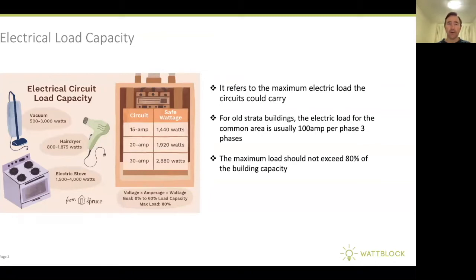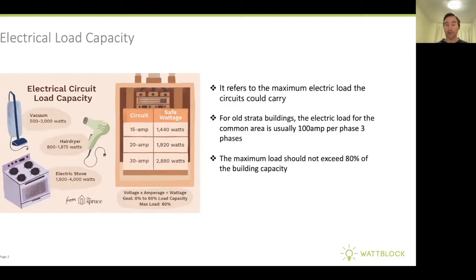The load capacity refers to the maximum electric load that the circuits can carry. On the left, we've got some examples of circuits and what a safe wattage is on those circuits. For old Strata buildings, the electrical load for the common area might be 100 amps per phase, three phase. The important point is the maximum load should not exceed 80% of the capacity of the circuit.